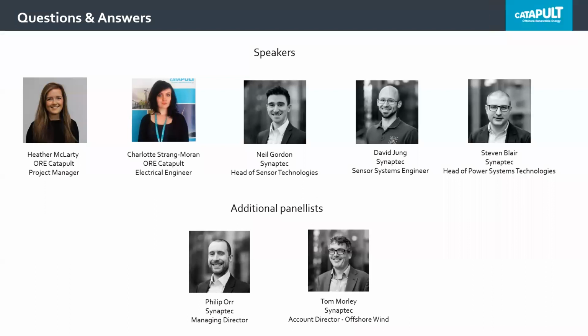Hopefully I would maybe just add one thing. So the OTDR obviously is looking at the fibre, and the main use of that from our perspective is to detect damage in the conductor, because they're so closely located that the fibre will likely be damaged by any failure in that cable. The question asks about monitoring the health of the fibres themselves. So OTDR was originally developed for that purpose, and we can use it for that as well. So if there's surveys to be done of the health of the fibres, that can also be done by the OTDR system. Yep, good point.